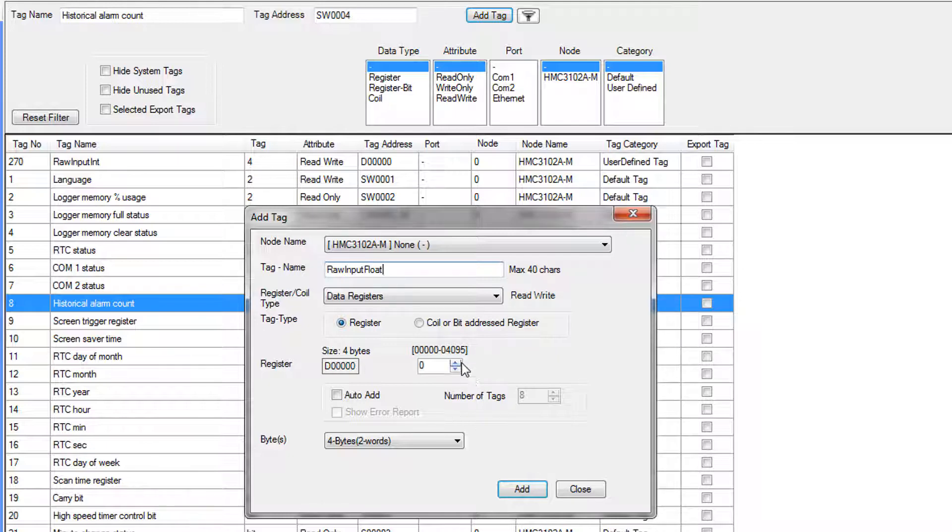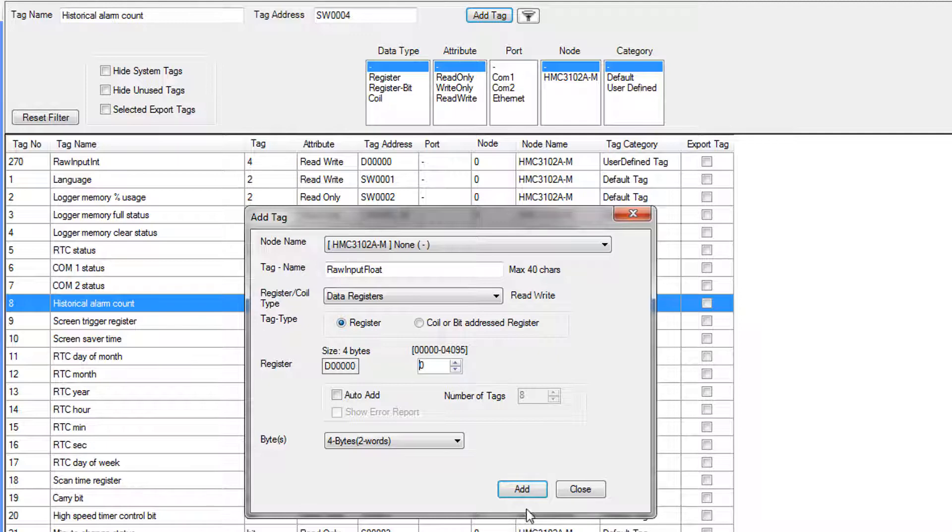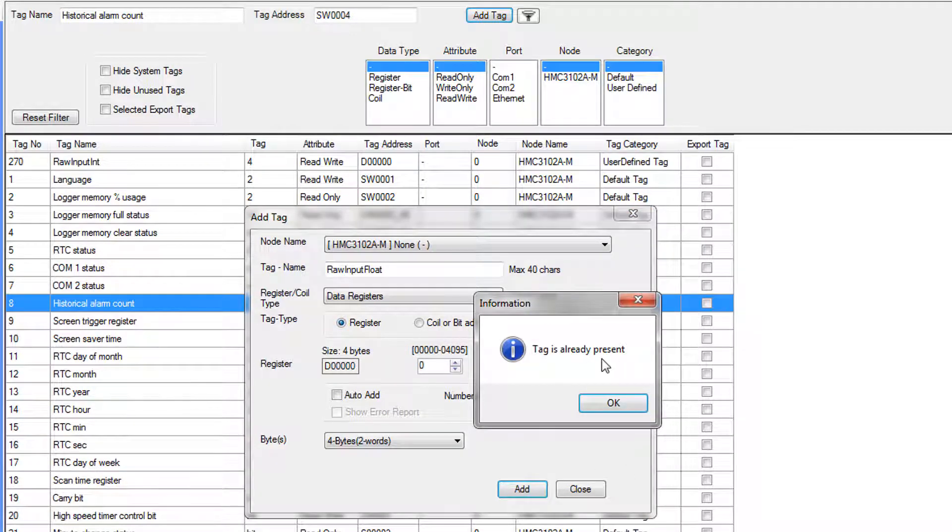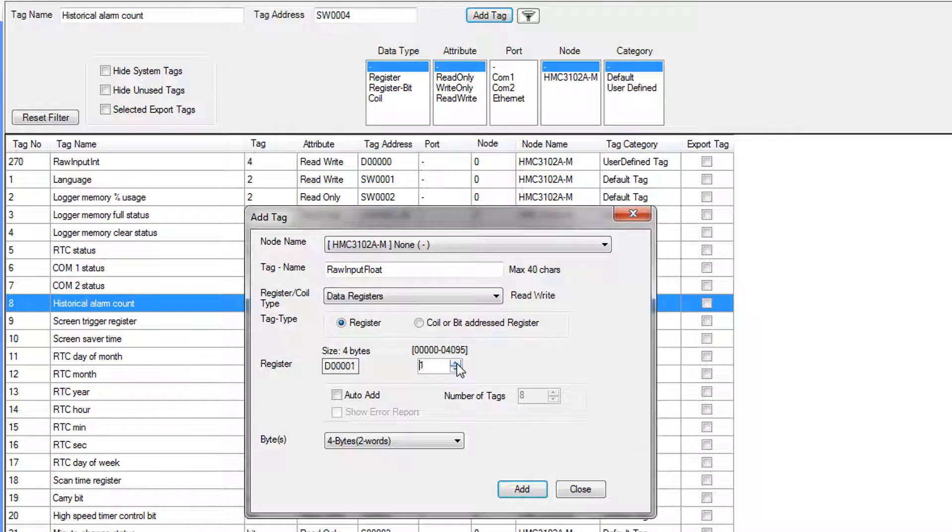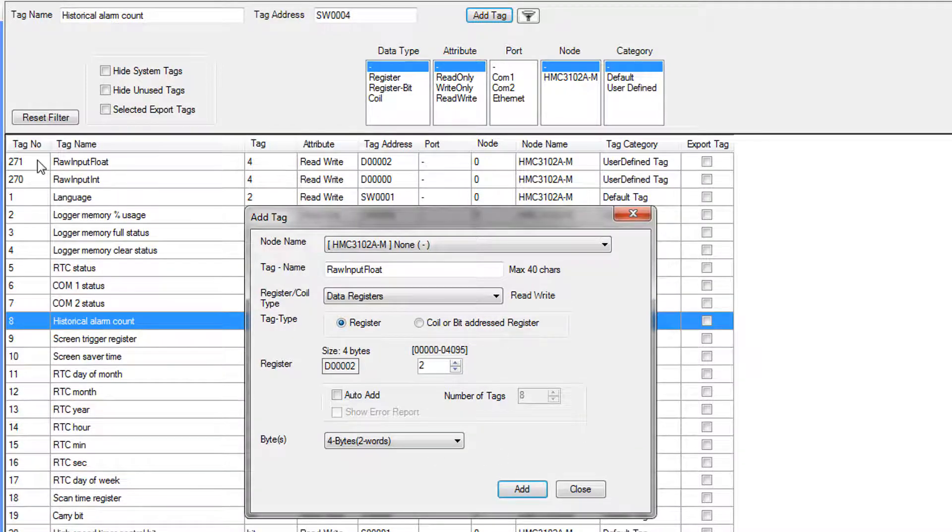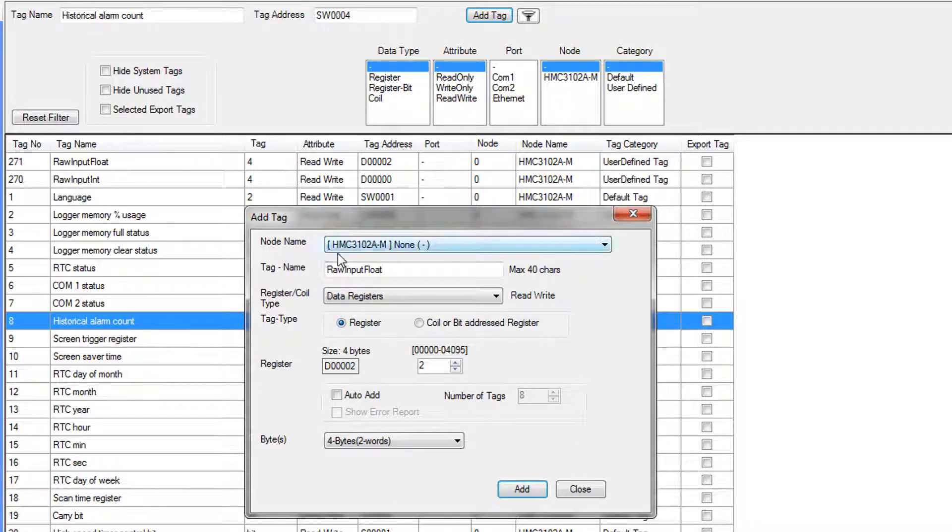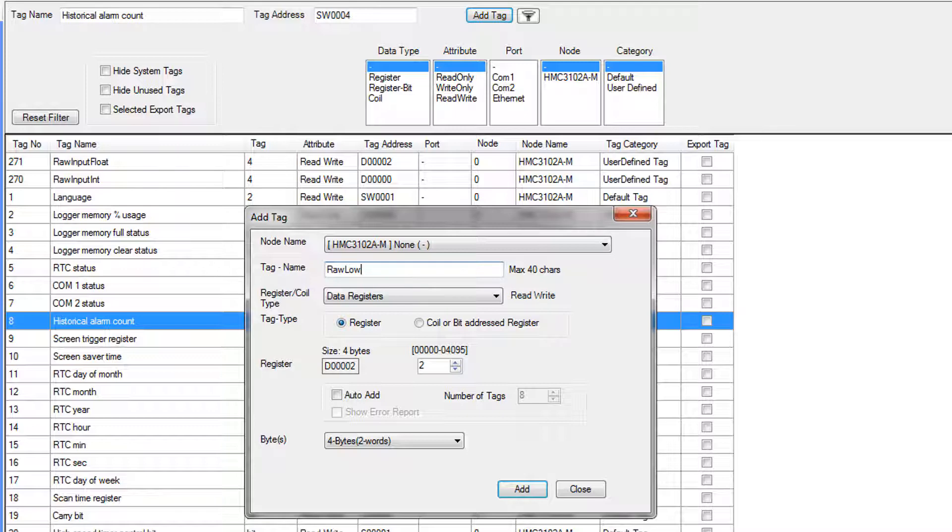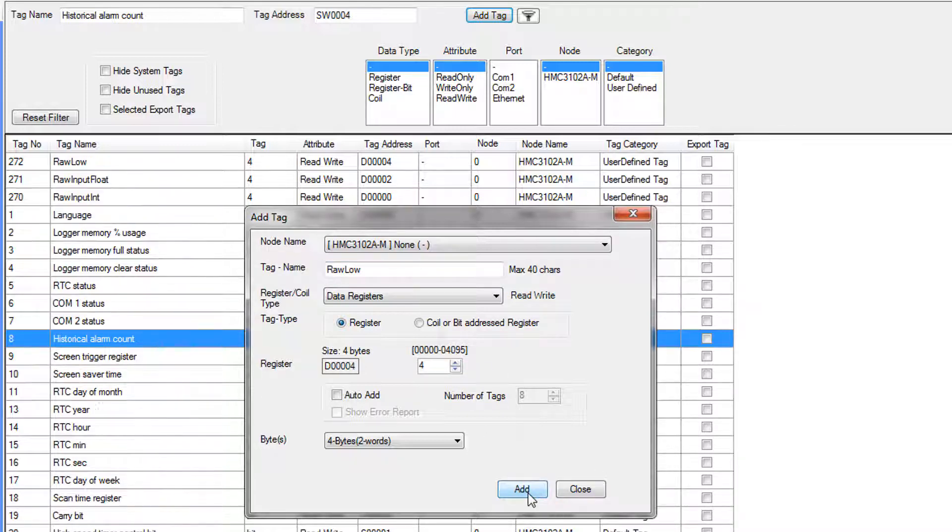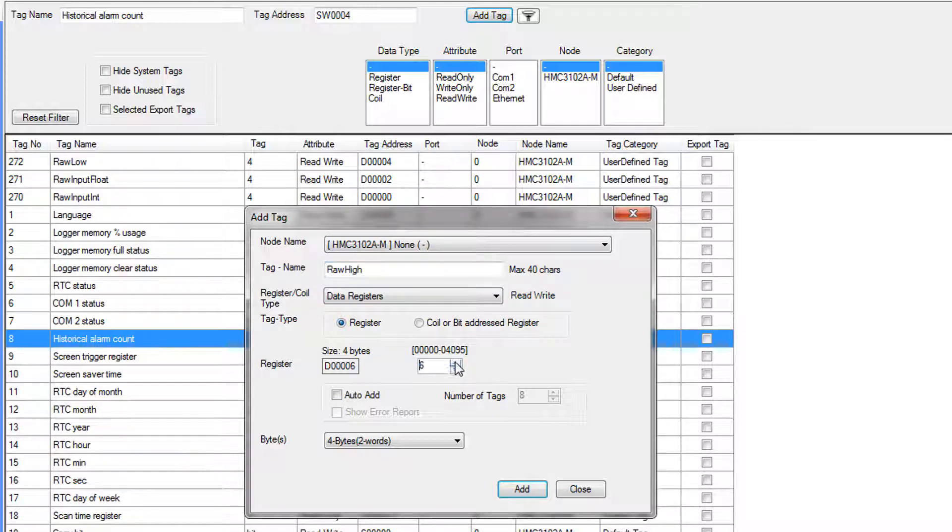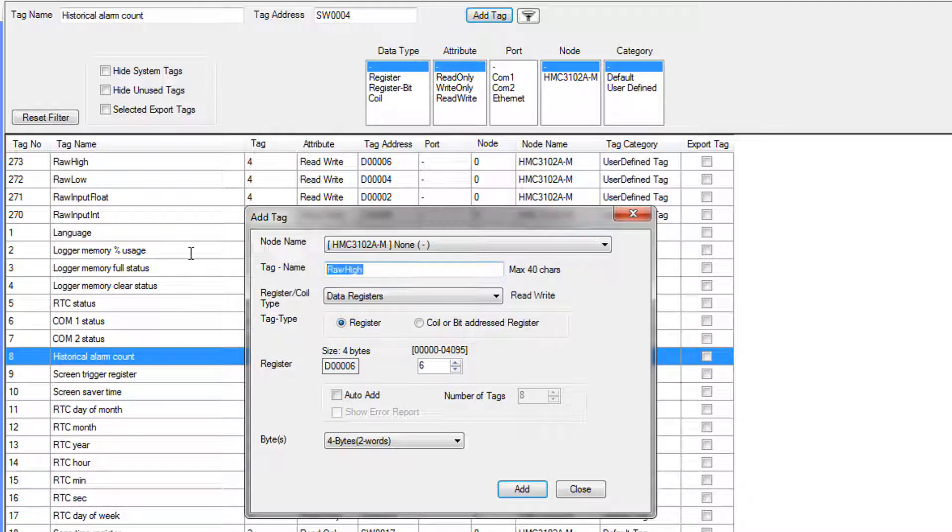The next tag is going to be RawInputFloat. We want this tag to be created at D2, but I'm going to show you what happens real fast if you forget to change your address. Tag already present. So you can't have two tags referencing the same memory address. Not allowed. So we'll increment by two and add. So RawInputFloat appears in the tag database. Next up is RawLow. Increment address by two and add.